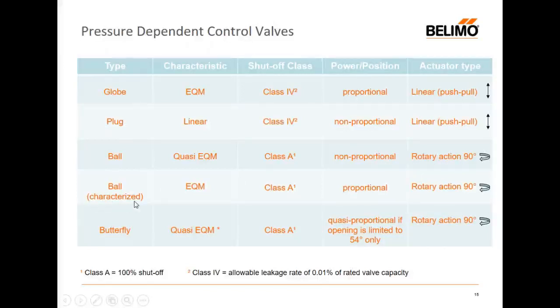Now, if we use a characterized ball valve, the one that we looked at earlier, we can have an EQM characteristic and we can also have class A shutoff. And of course, because it's characterized, we get our proportionality, which is very important for modulating control, and we get the benefit of a rotary action, which is through 90 degrees and not fighting the pump, but merely rotating. So we get quite a high shutoff value because of that. And then we move to butterfly valves, another rotary valve. Again, quasi EQM in its natural state. Class A shutoff for sure, which is good, but quasi proportional. Now, because it's quasi proportional, if we decide to limit the opening of the valve to around 54 degrees, we get an almost EQM characteristic. So we can almost get proportionality, and we are getting a rotary action.